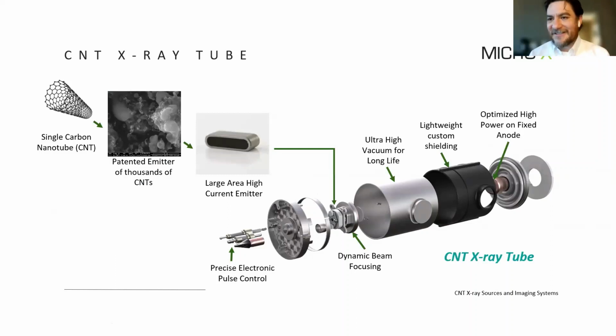The spectrum is a conventional tungsten spectrum. We use tungsten anodes for the tubes that we are currently designing. There's nothing in the physics that says we couldn't use another. We could use a moly if we were going to make a mammography tube. There's nothing that says it has to be tungsten, but for the applications that we're using, we believe tungsten is the best anode material, and you get a conventional tungsten spectrum from the tube.